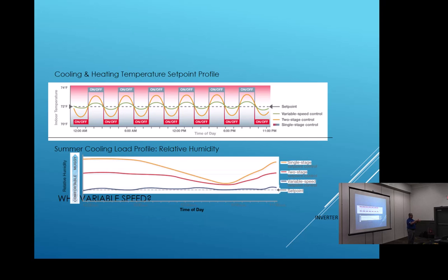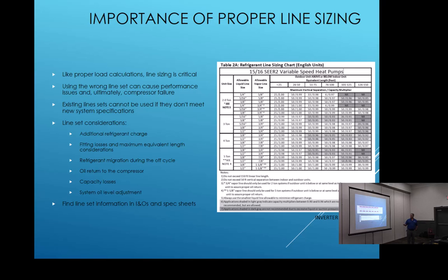This kind of shows you what our single stage is, our drop-off from our two-stage, and our fully variable speed, and maintaining our temperature control down here. Okay, this is something new this year for our line set chart. If you remember, if you've been doing Ring for a while, they have always said you can never, ever, ever, never use a 1 1/8 line set. Well, guess what? You can now. Only on a 5-ton. Only on a 5-ton.